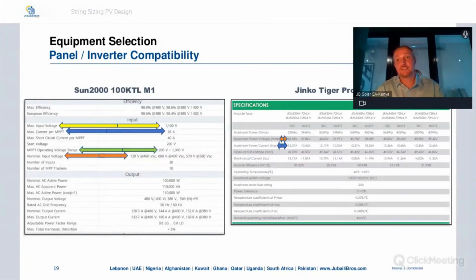That's more than 26. If you exceed the max current per MPPT, it will not damage the inverter. You will just see current clipping. It will not operate very efficiently or at maximum efficiency. But this is fine. It's very, very close. And the peak hours of sunlight do not happen often and they do not happen for long times. So this is fine.